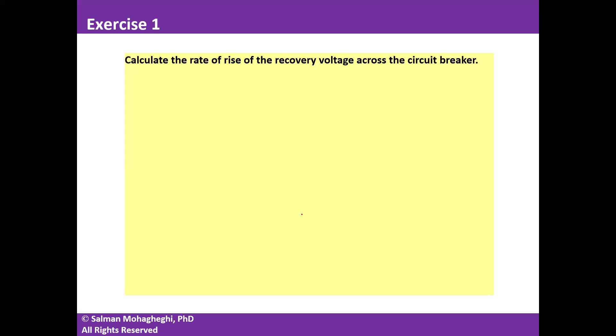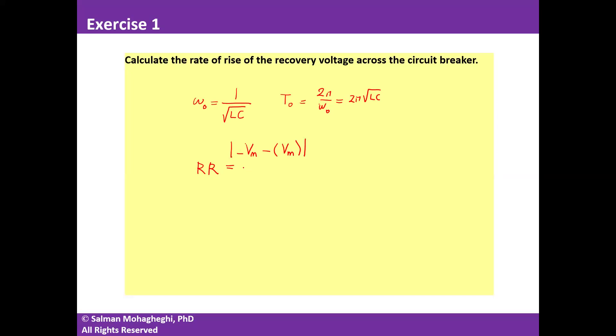The frequency of oscillation between the inductor and capacitor is ω₀ = 1 / √(LC), so the period of oscillation is T₀ = 2π√(LC). The rate of rise is 2·V_M divided by T₀/2, which equals 2·V_M / (π√(LC)). If this is higher than the dielectric strength of the circuit breaker, you're going to have a re-strike.